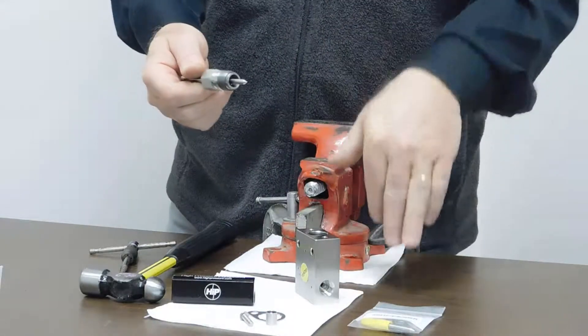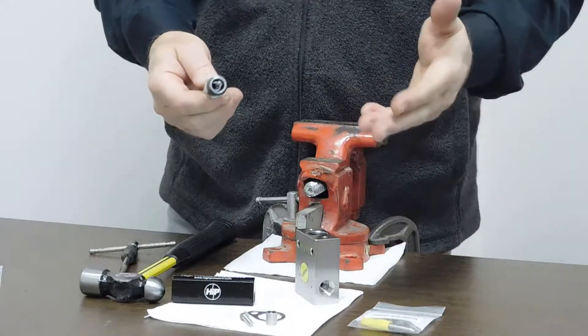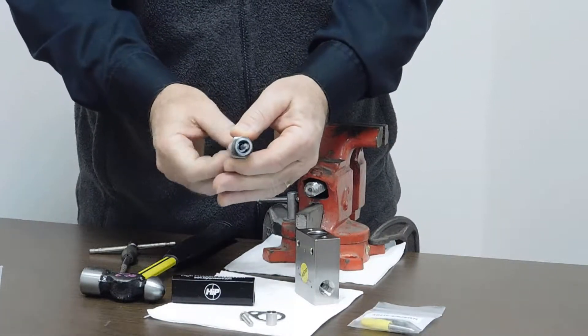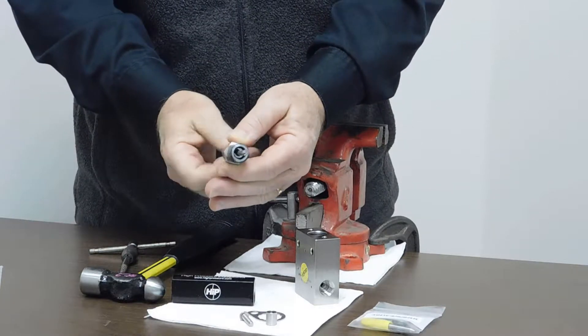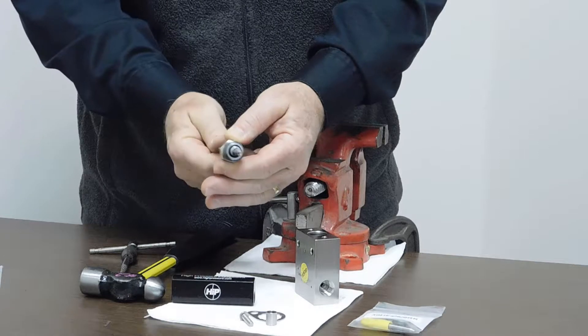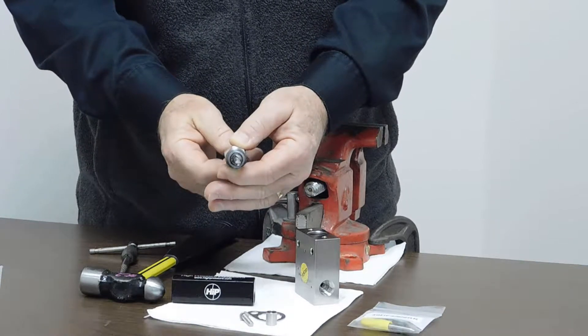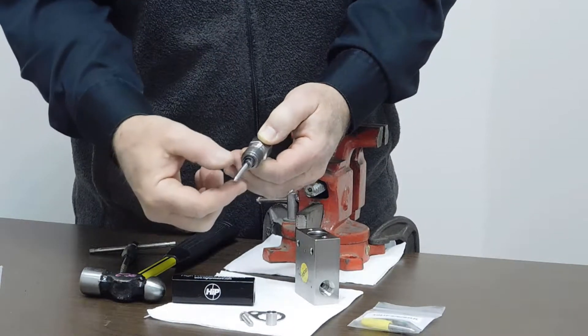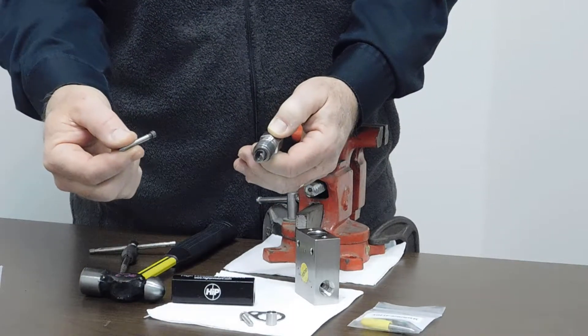All right, in this case, all the washers stay down inside the block. So the next step is to push the stem forward and remove the lower stem. The lower stem is a slotted design that actually fits up inside the upper stem assembly. So the upper stem has a slot and the lower stem has a mating part that goes down inside the slot and you basically just pull it out like that.